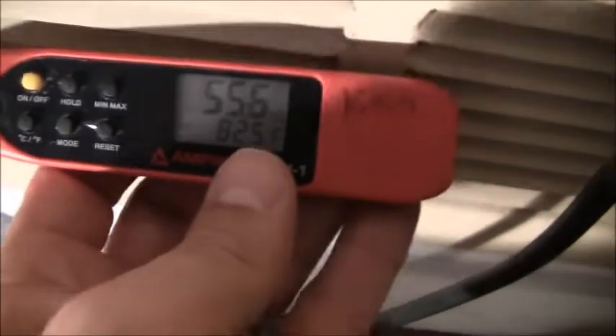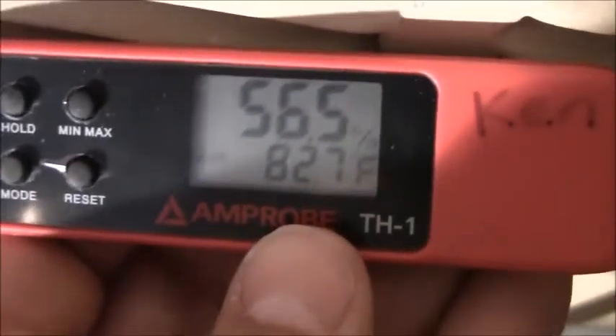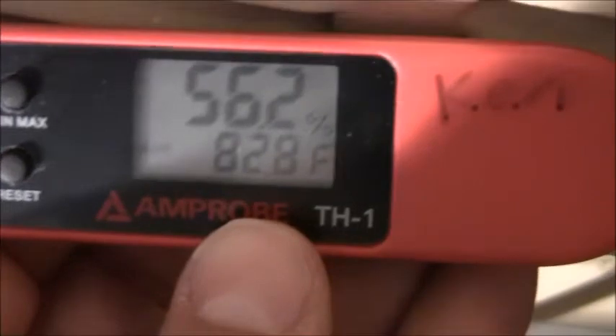0.125. Now, as long as we're here, let's get our return air dry bulb and wet bulb. I got my thermometer here, vents are open on it, and let's go ahead and see what that is. Okay, so the dry bulb temperature is showing 82.7. Oh, come on.